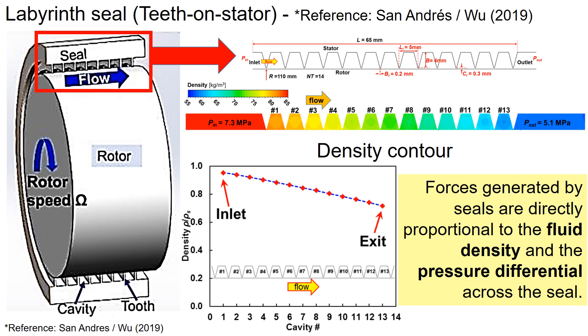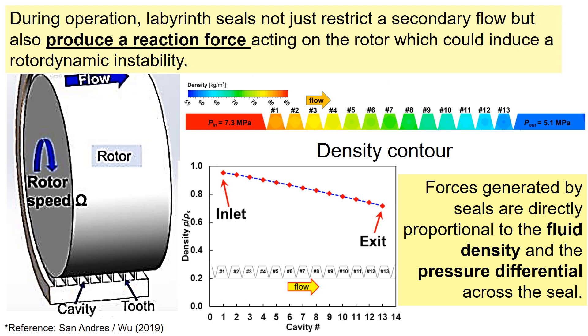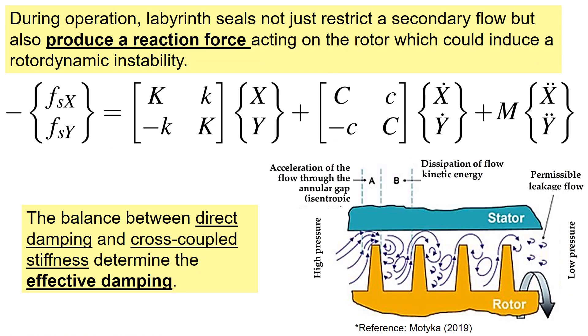It is important to note that forces exerted by the seals are directly proportional to the fluid density and the pressure differential across the seals. During operation, labyrinth seals not only restrict the secondary flow but also generate reaction forces on the rotor, which can induce rotor dynamic instability. Forces exerted on the rotor can be described in terms of direct stiffness, cross-coupled stiffness, direct damping, and cross-coupled damping.